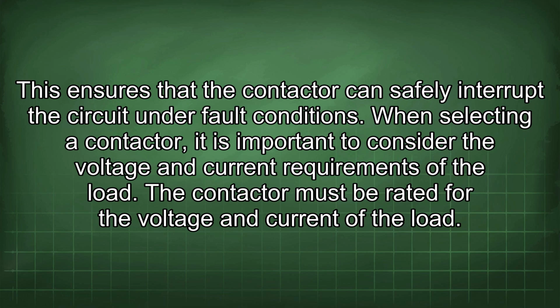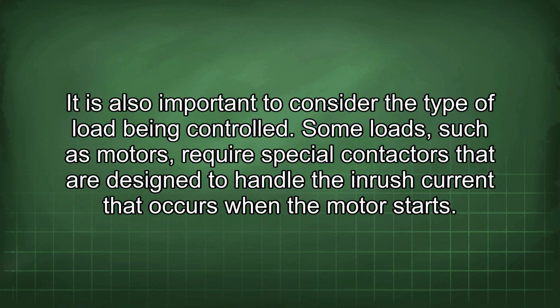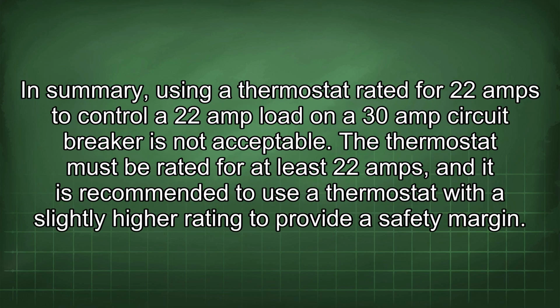When selecting a contactor, it is important to consider the voltage and current requirements of the load. The contactor must be rated for the voltage and current of the load. It is also important to consider the type of load being controlled. Some loads, such as motors, require special contactors that are designed to handle the inrush current that occurs when the motor starts. In summary, using a thermostat rated for 22 amps to control a 22 amp load on a 30 amp circuit breaker is not acceptable. The thermostat must be rated for at least 22 amps, and it is recommended to use a thermostat with a slightly higher rating to provide a safety margin.